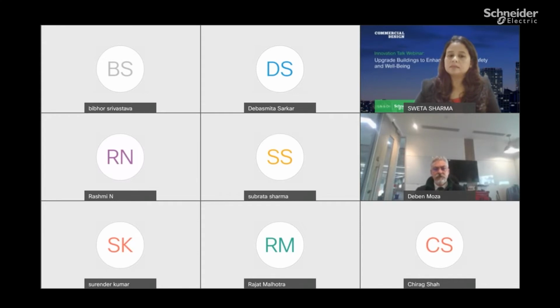Generally, as per ASHRAE standards, people use, and we are also using, but now we have started designing all our buildings with even 30% extra fresh air, giving more fresh air to the building. This has to be automatically controlled based on the BMS. This is the new demand ventilation, so we always try to maintain the CO2 level in the office area at ambient plus 350. This is one of the good features of a Class A building, we can say.